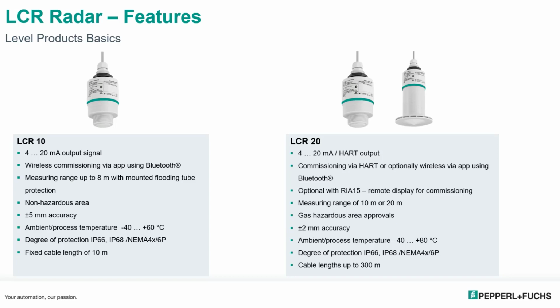The LCR-20, we offer this with a 4 to 20 milliamp output with HART output. So you can commission it via the HART or PACware or through the wireless Bluetooth. You can get this up to a 20 meter sensing range. We do have gas hazardous approvals for the LCR-20s. The ambient temperatures are minus 40 to plus 80, so it's a little bit better than the LCR-10s.